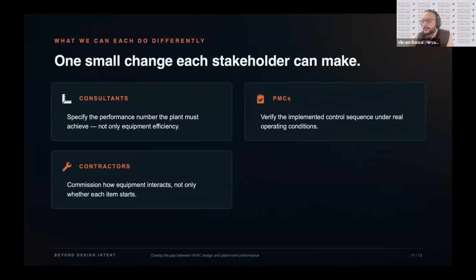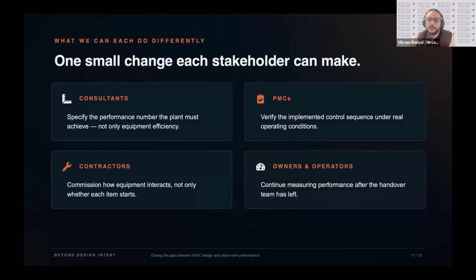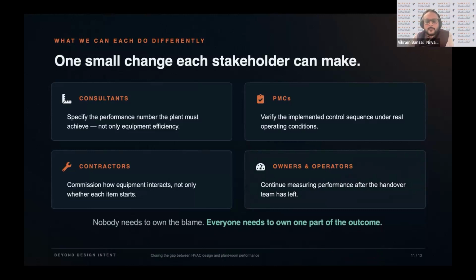For the PMCs, the implemented control sequence has to work under the operating conditions, because in northern India what I have seen is that when we hand over the building, the load for which the entire system is designed is not there. It takes almost a year or so to get the entire load. So some control should be there to check this performance when the peak load is there, and the owners and the operators should continually measure the performance after the handover. The intent is not that somebody should own the blame, but that everybody should own one part of the outcome so that we can deliver what was intended during the design stage.